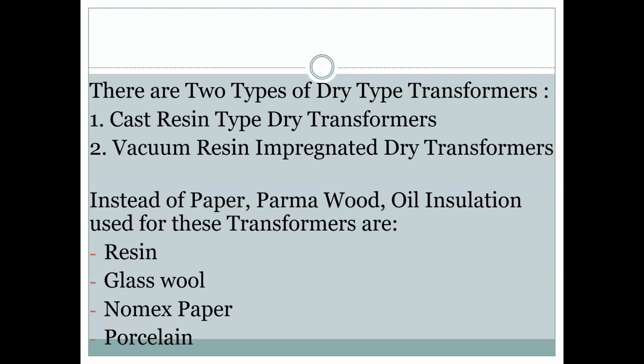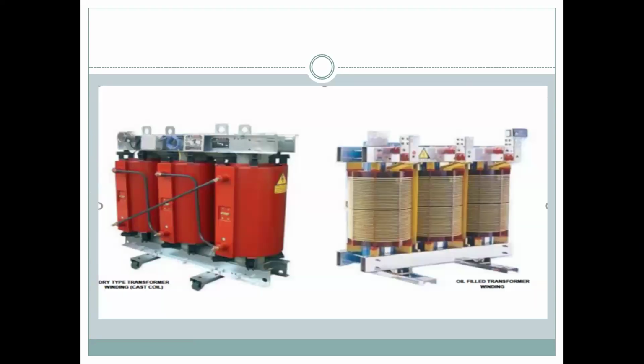There are two types of dry type transformers: cast resin type and vacuum resin impregnated dry type transformers. Here resin, glass wool, Nomex paper and porcelain are used as the insulation. Next slide. These are the coil assembly of the dry-type transformer. This is the cast resin type, and this is the vacuum resin impregnated type. In vacuum resin impregnated type, resin is used as the rigid body. That means it does not act as an insulation. Insulation is done using Nomex paper, glass wool, and this type of material. It is a high grade of insulation, class C type, but we declare it as class F and class H insulation. And here cast resin is also an insulation as well as forming the rigidity of the transformer. So this is how the dry type transformers look.